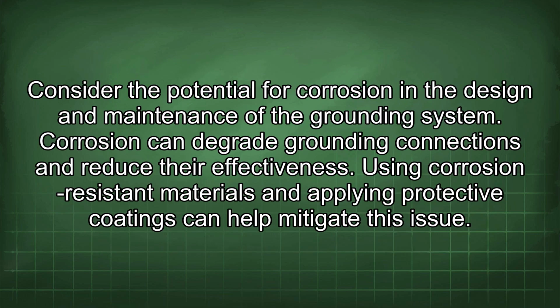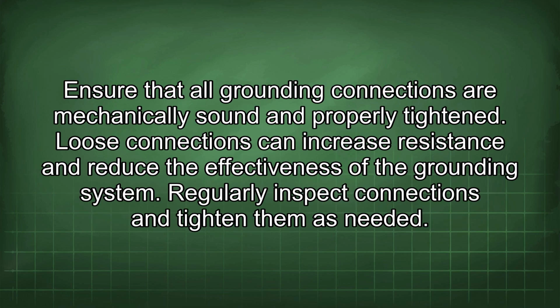Consider the potential for corrosion in the design and maintenance of the grounding system. Corrosion can degrade grounding connections and reduce their effectiveness. Using corrosion-resistant materials and applying protective coatings can help mitigate this issue. Ensure that all grounding connections are mechanically sound and properly tightened. Loose connections can increase resistance and reduce the effectiveness of the grounding system. Regularly inspect connections and tighten them as needed.